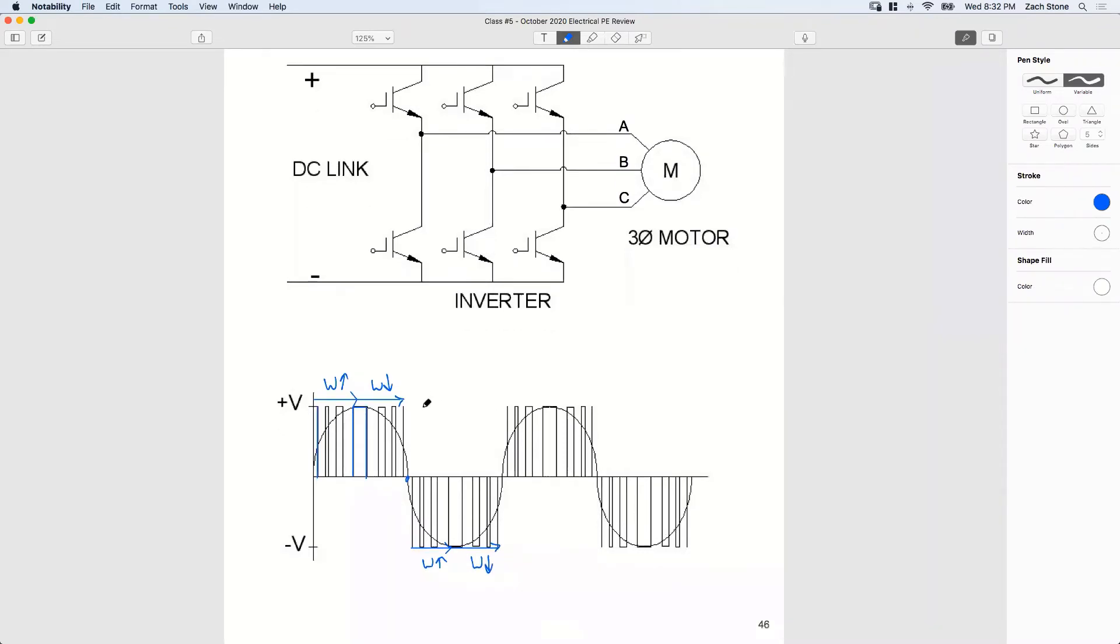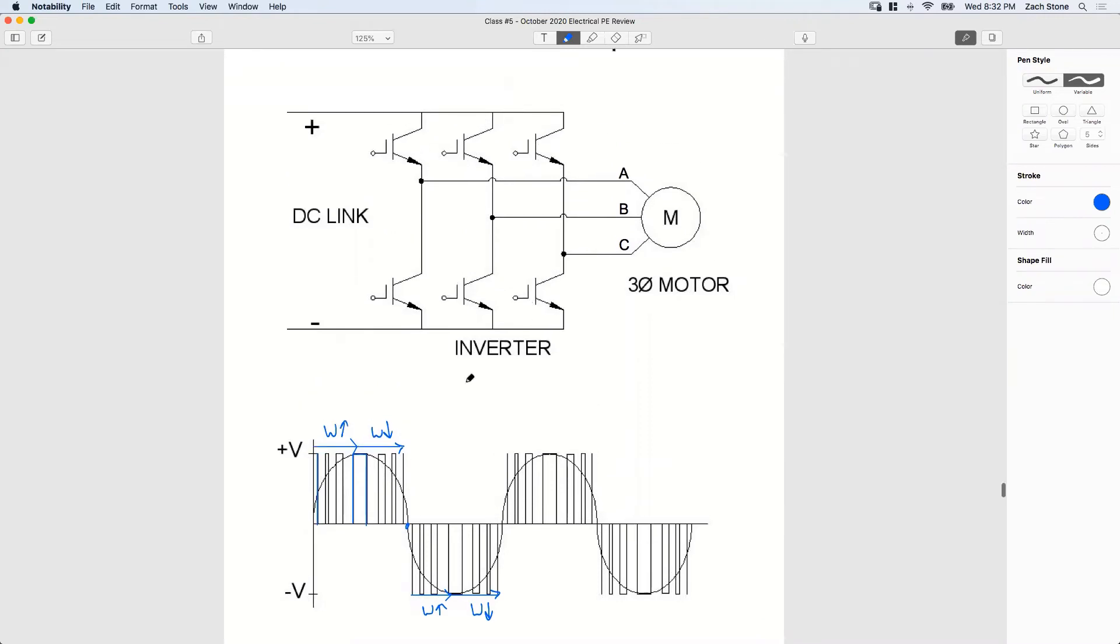Remember when we calculated the average value? When we use IGBTs to control the speed of a motor, we're really not giving it a true AC sine wave. So the sine wave in the background, that's just to kind of give you a visual guide, right? The motor is getting this chopped, pulsed width voltage.